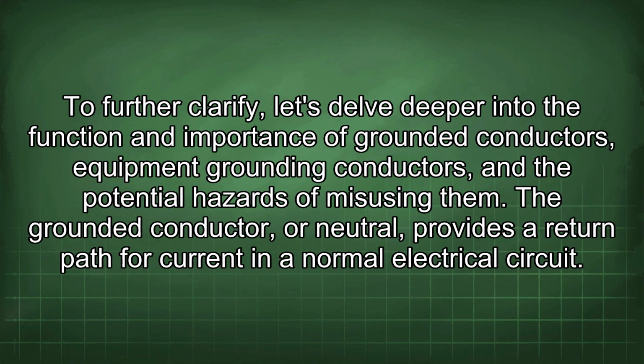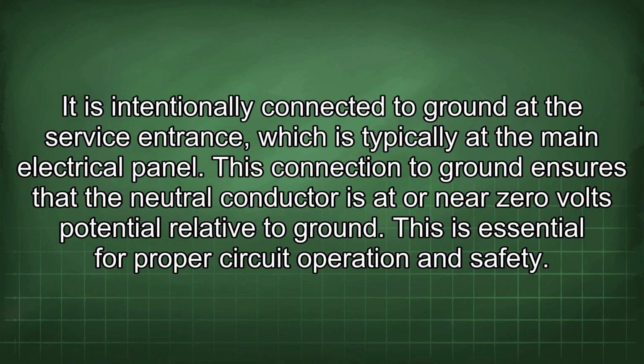To further clarify, let's delve deeper into the function and importance of grounded conductors, equipment grounding conductors, and the potential hazards of misusing them. The grounded conductor, or neutral, provides a return path for current in a normal electrical circuit. It is intentionally connected to ground at the service entrance, which is typically at the main electrical panel. This connection to ground ensures that the neutral conductor is at or near 0 volts potential relative to ground. This is essential for proper circuit operation and safety.